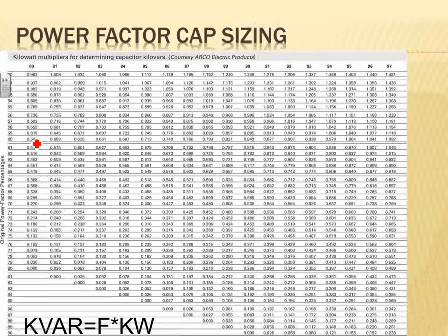So if you take, for example, my power factor here, let's just say a power factor of 75. That's my original power factor. When you correct, you typically correct in the 90s. You don't go all the way high here, because if you go to 97, you are taking a chance of going leading power factor, which creates a higher voltage in your system, which also has a problem. So I'm going to go correct from 75 to 92.